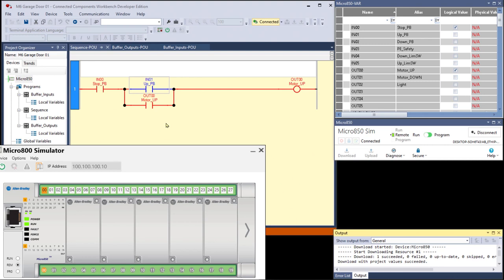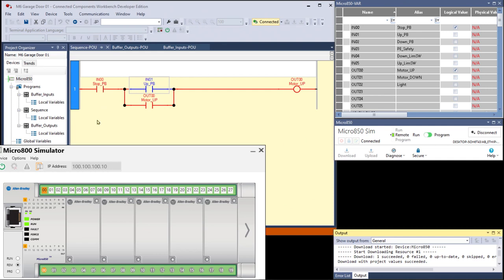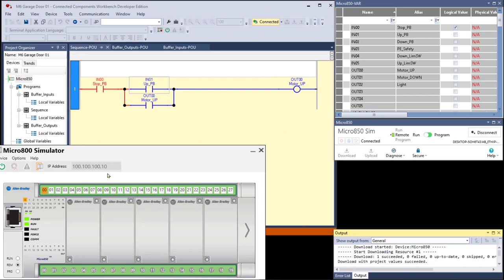We're working with three bits in memory here. Two of them happen to be actual I/O input devices. Two push buttons and then we have an output device that is either a starter that's going to run the motor in the up direction or it's a direct connect for 115 volts. And once again I want to mention that this represents a normally closed momentary push button. And if it's a normally closed push button and it's not pressed then it's passing voltage to this screw terminal and it's on. If you press the button it goes off and then when you release it goes right back on.